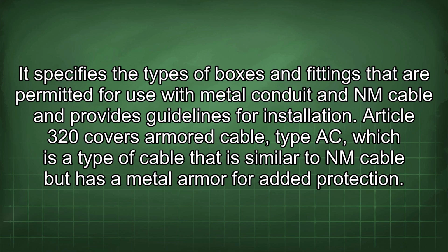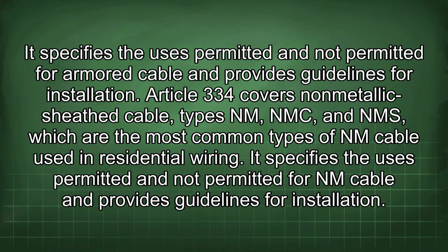provides guidelines for installation. Article 320 covers armored cable type AC, which is a type of cable that is similar to NM cable but has a metal armor for added protection. It specifies the uses permitted and not permitted for armored cable and provides guidelines for installation. Article 334 covers non-metallic sheathed cable types NM, NMC, and NMS, which are the most common types of NM cable used in residential wiring. It specifies the uses permitted and not permitted for NM cable and provides guidelines for installation.